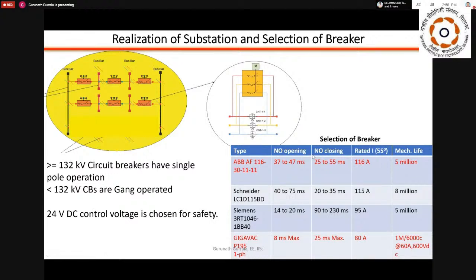And another thing that we have used is this: if you look at the operation of substations below 132 kV, most of the time they are gang-operated circuit breakers. That means all 3 poles or all 3 phases will be opened or closed simultaneously. You don't have independent operation of the phases. Whereas if you go above 132 kV, most high voltage substations have independent pole operation, where you will do auto reclosing if there is a short duration fault, and then that particular phase will automatically recover the system. If it doesn't work, then you will completely trip the system.